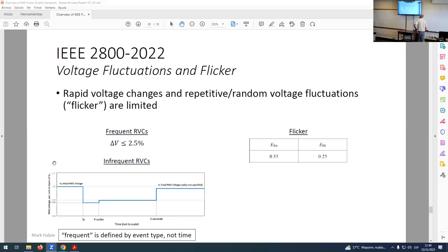And this would significantly underutilize any system's ability to absorb fluctuation or flicker disturbance, okay? It's way too conservative. Okay, but it is what it is, okay? Let's see, as far as RVCs are concerned, now, for 2800, the interconnection voltages are higher. We're talking about transmission now. So the frequent rapid voltage changes are limited. The step change is less than it was in 1547, so 2.5% rather than 3, okay?